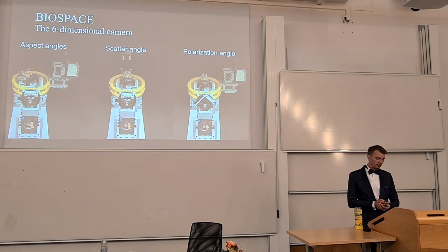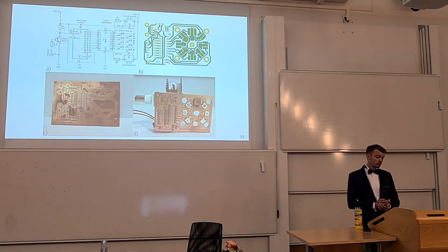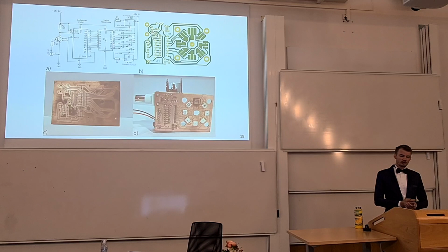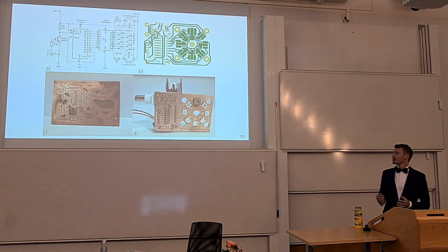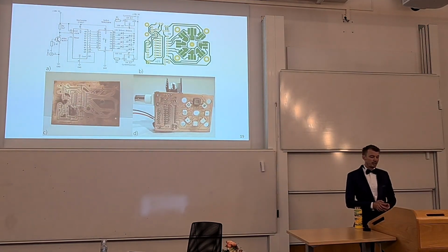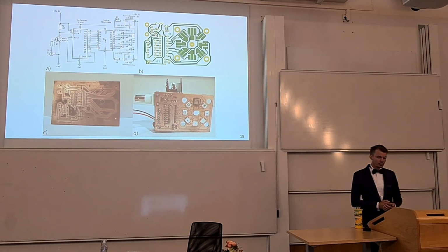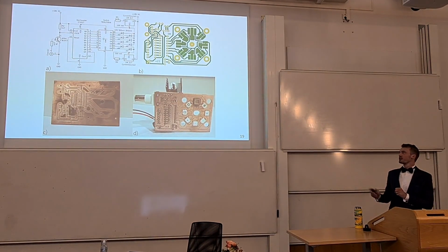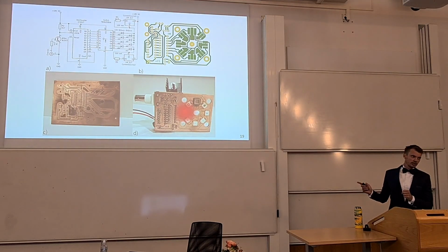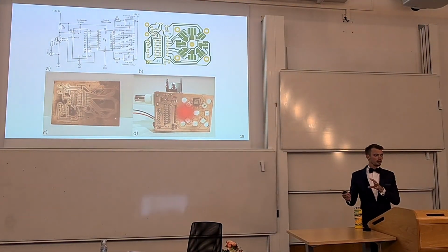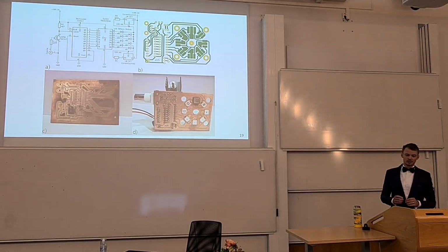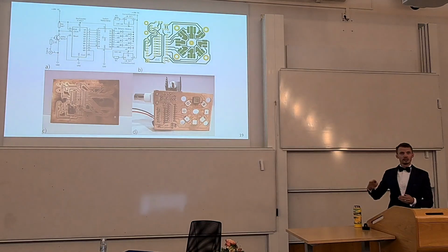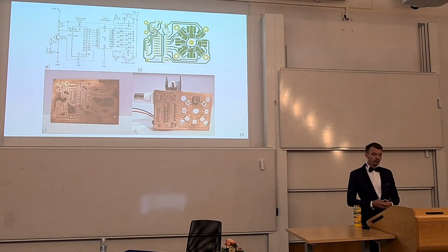And to get the wavelength, we've designed a specialized light source. This works on a principle called LED multiplexing. The light source has 8 LEDs with different colors, different wavelength bands, and it's synchronized with the camera. With each image that the camera takes, the sample is illuminated by one of these LEDs. Then the camera takes another image, and we illuminate the sample with the next LED. It goes on like this, so that we take these 8 different images and one dark one, and then we have built up a multispectral image of our sample.